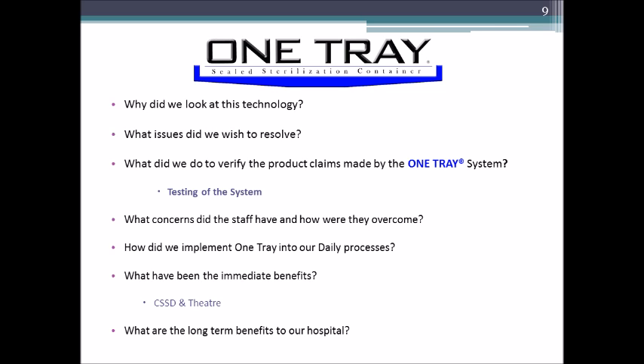There are, as you can see down below there, long-term benefits of cost savings. If you think about the way that the sterilizer works, when we're running all these trays in there, my typical cycles in the hospital that I'm in, for the steam parameters, are 4 minutes of exposure time with 45 minutes of dry time. That just was what worked for our facility, and now with this system, like I mentioned, when we get those 25 trays dropped off and we run these One Trays through the autoclave system, we're eliminating that 45 minutes of dry time.